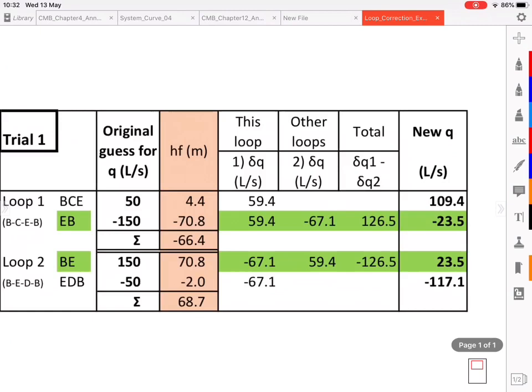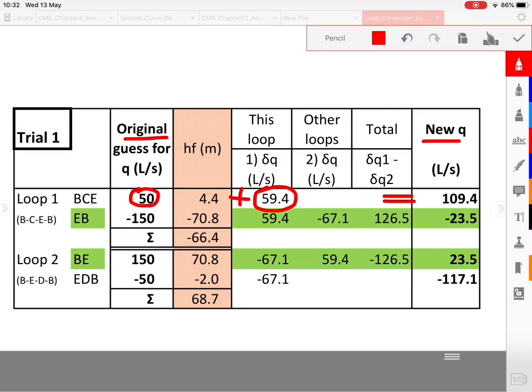Finally, we need a new Q for every pipe. It'll be the original Q for that pipe plus the correction factor. For shared pipes, we would have, in this example, minus 150 plus 126.5, which equals minus 23.5.